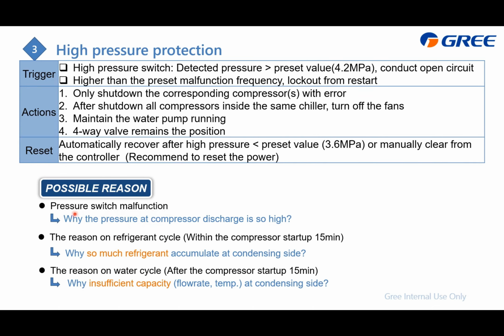And maybe this pressure sensor is a malfunction. And after that, we can consider the reason in the refrigerant cycle. Within the compressor start up in 15 minutes, you can focus on this refrigerant cycle, which is why so much refrigerant accumulated at the condensing side. And after 15 minutes, just focus on the water cycle. Why not insufficient capacity, like the water flow rate or the temperature is not that good at the condensing side.